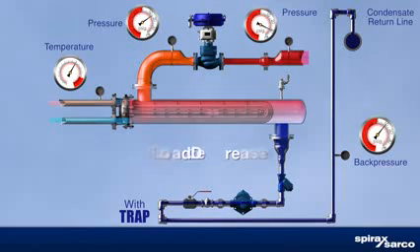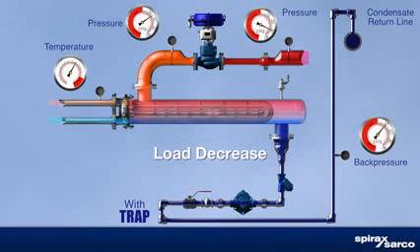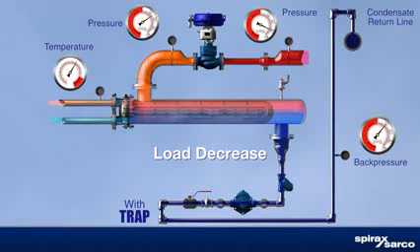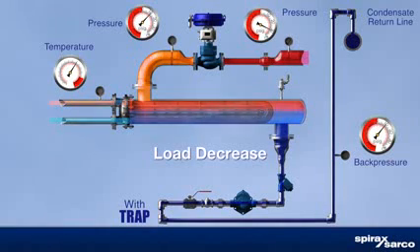Under reduced heating load, the control valve throttles down, reducing the steam pressure inside the heat exchanger. This also reduces the differential pressure across the steam trap, making the trap unable to remove the condensate.